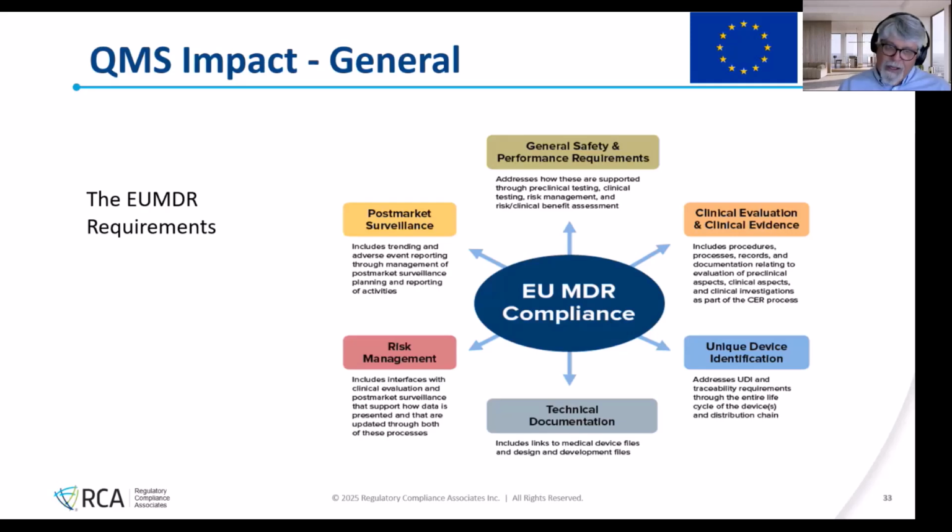Clearly, the technical documentation is the output of the quality management system that provides objective evidence that the purpose of the quality management system, or design intent, is being met. Practically, the design intent is that the device is safe for intended use, has effective performance, and we meet all applicable regulatory requirements. This is what the technical documentation is about. Your technical documentation will get audited. So just be aware of that.